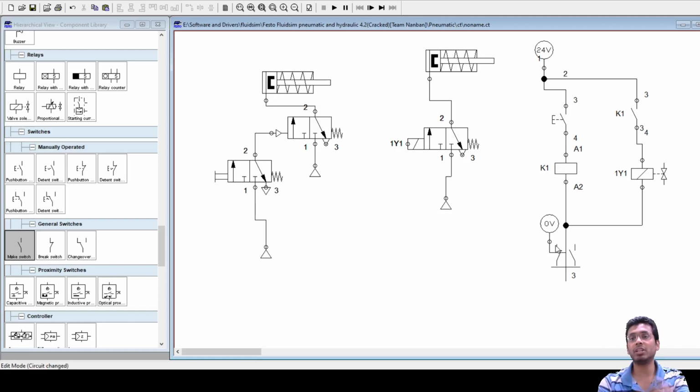That means you can use a relay. You will energize that relay with this 24 volt system, whereas the normally open and normally closed contacts of that relay may work in altogether different electrical circuits, ranging over different voltages and different current ampere ratings. So this is your indirect control of a single acting cylinder.